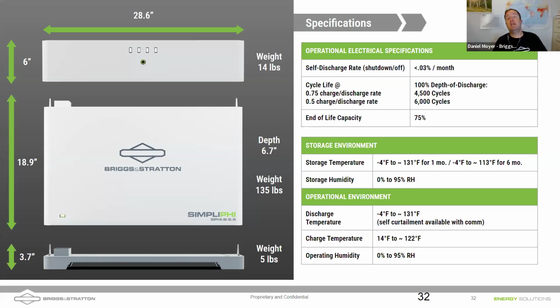Cold weather has been a big problem in this industry. We're able to go down to 14 degrees Fahrenheit on the charge cycle. It's going to start to curtail as it gets colder. So if you're charging between 14 and 32, you're at a C over 5 rate, which means a 5-hour charge cycle, which is normally sufficient for most homeowners anyway.